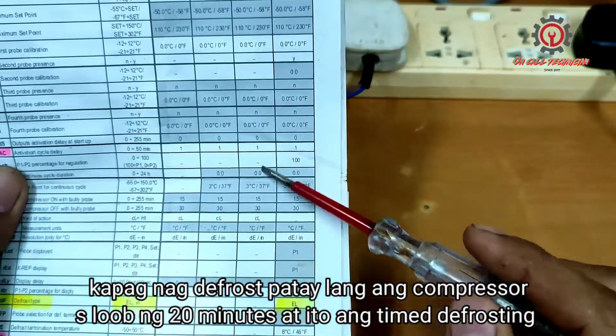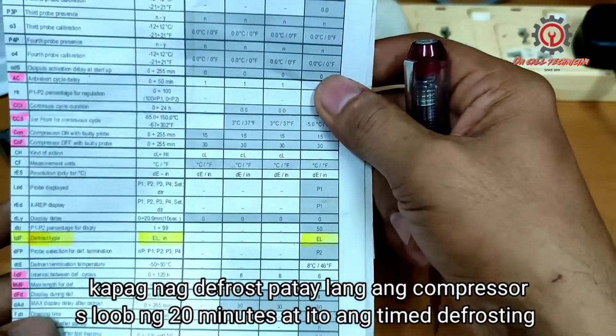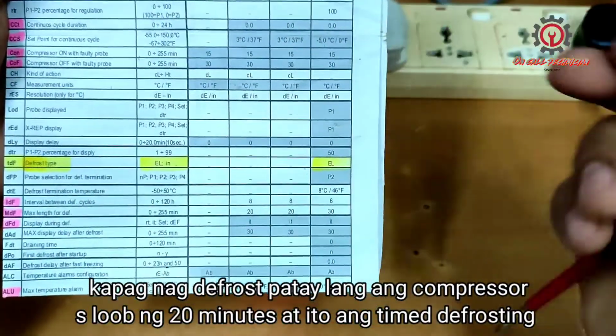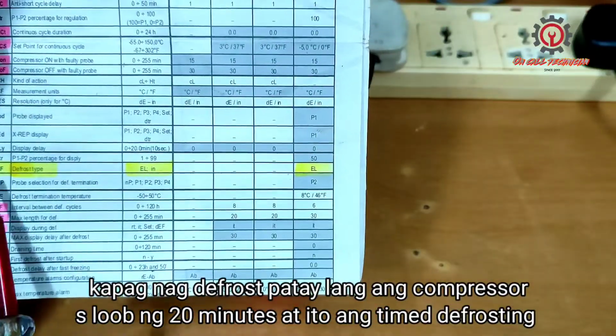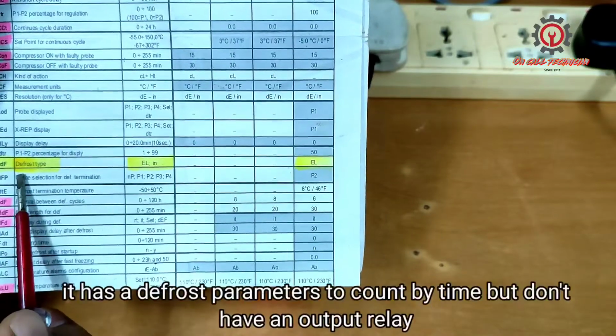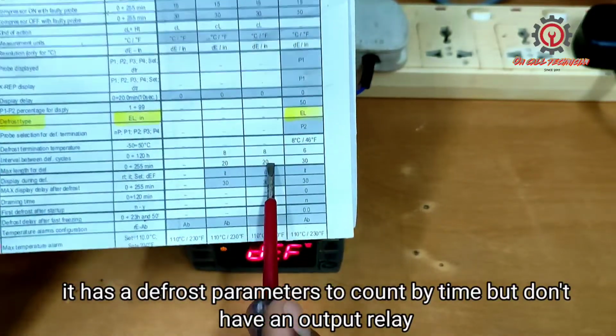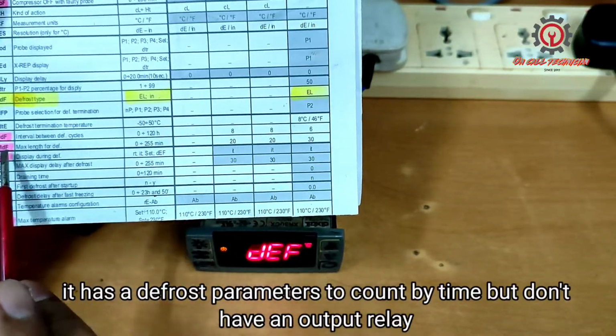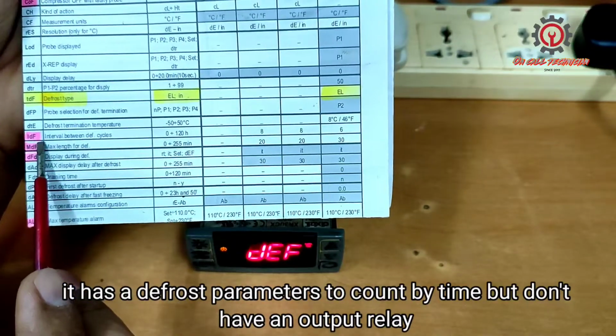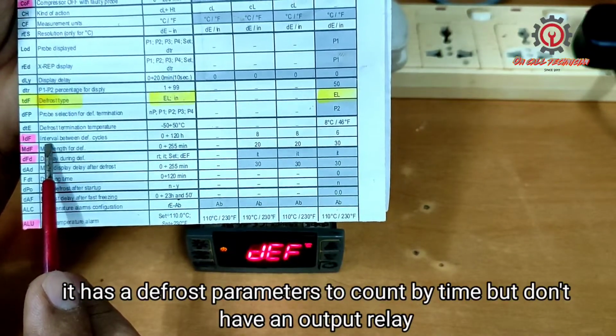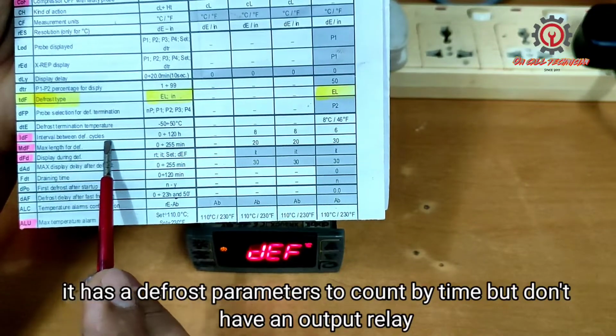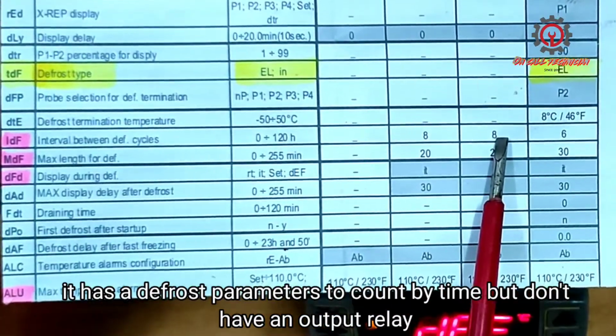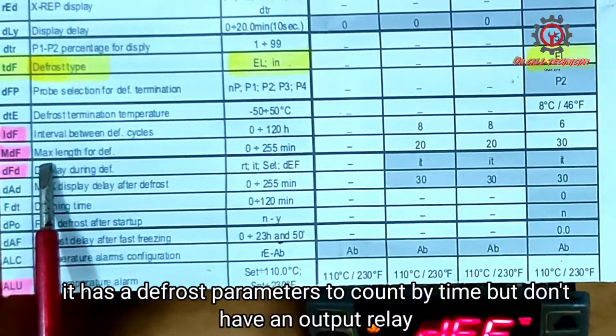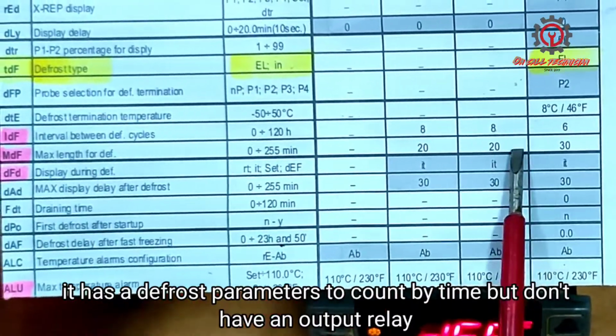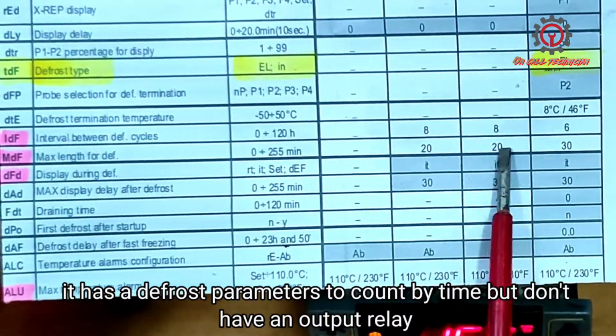And we proceed to the defrost parameter, and under here, so we only have here the IDF. This is the interval between defrost cycle. The default is 8, and for the max length of defrost, 20 is the default.